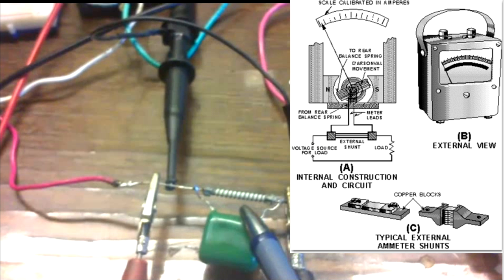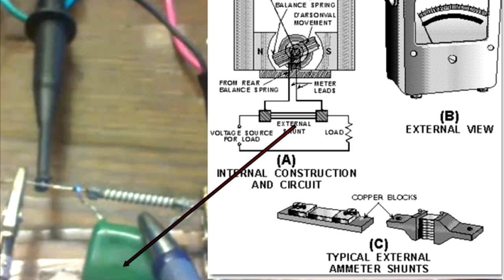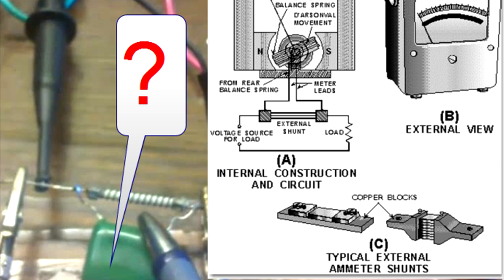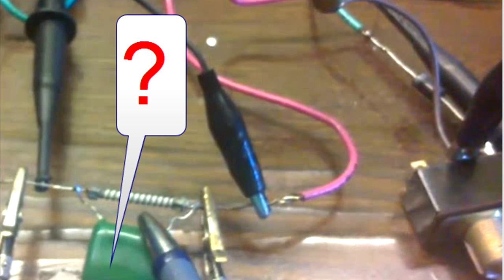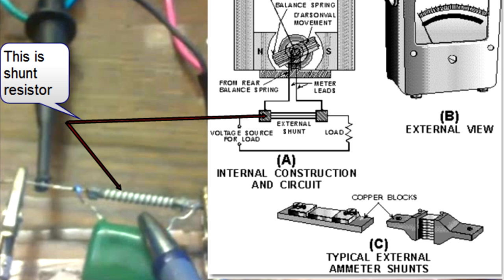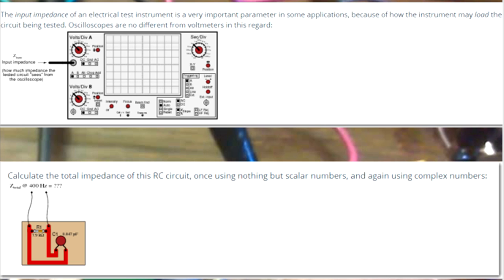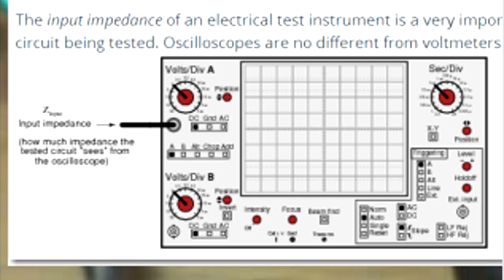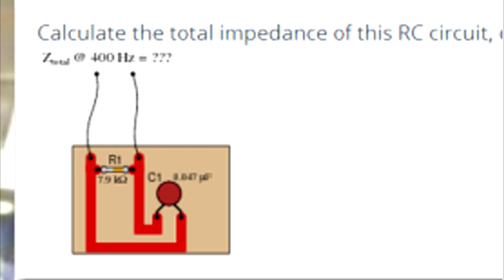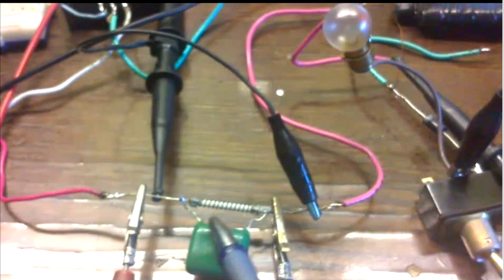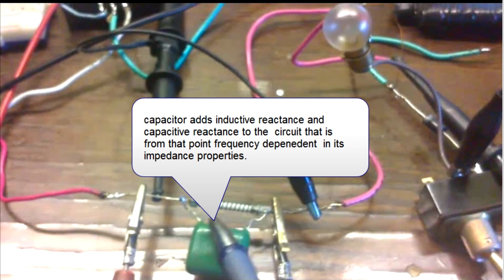The problem with measurement that I may have here is that the typical shunt doesn't have a reactive component. It is pure resistance. That means that whenever we connect a capacitor into the circuit, we're creating a filter, which then reacts based on the capacitive component of the capacitor, its value, and also the frequency delivered, or frequency variation. So again, the problem is that we're no longer dealing with pure resistance, we're dealing with a dynamic arrangement. The dynamic arrangement depends strictly on the shape of the signal at the given delta T, or time frame, at which we take the measurement. So then we need to have averaging in order to find out if that's what is happening.